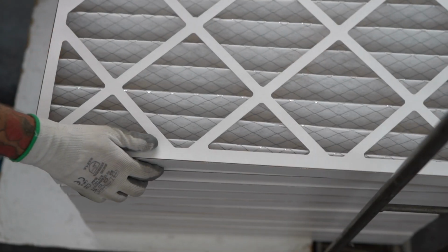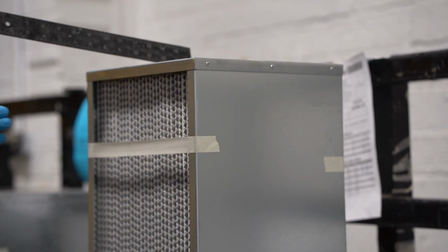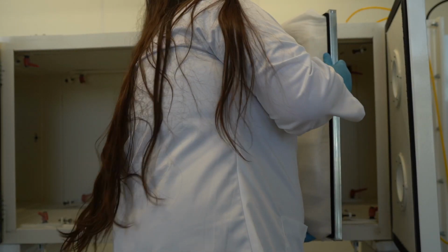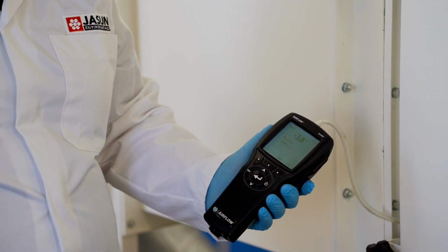Different types of filters have different lifespans depending on the type and application. What they're used for and how often can affect the life of each filter. A new clean filter has an initial pressure drop or resistance. When this increases to an advised dirty limit, by simply doing its job collecting contaminants, the filter is becoming blocked and should then be replaced.